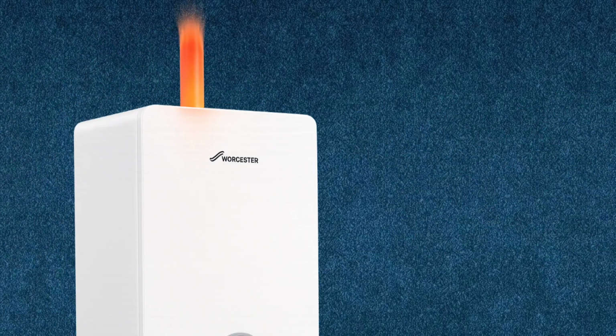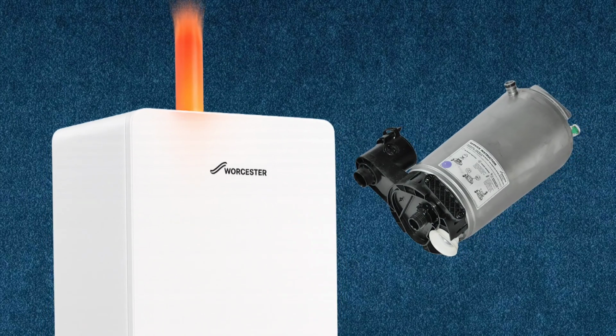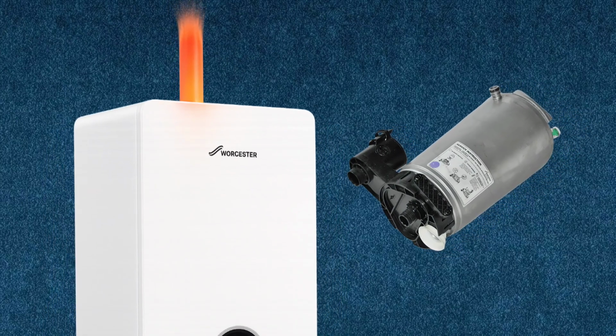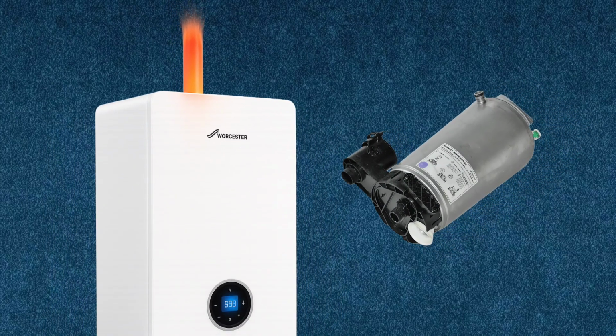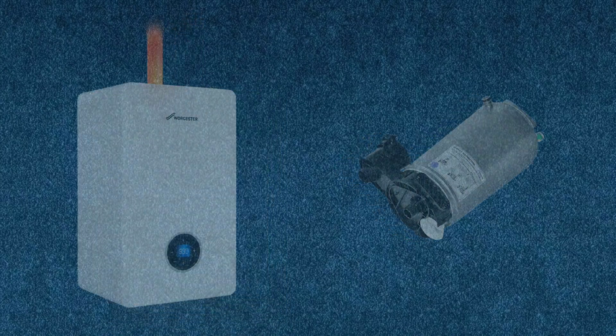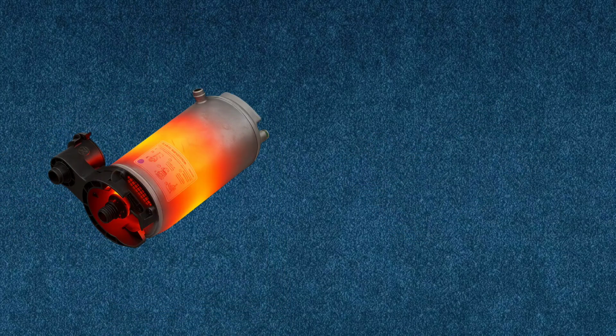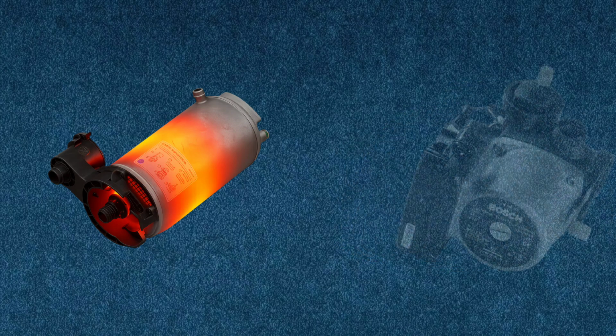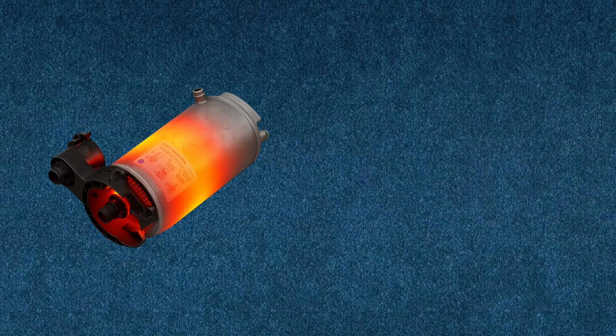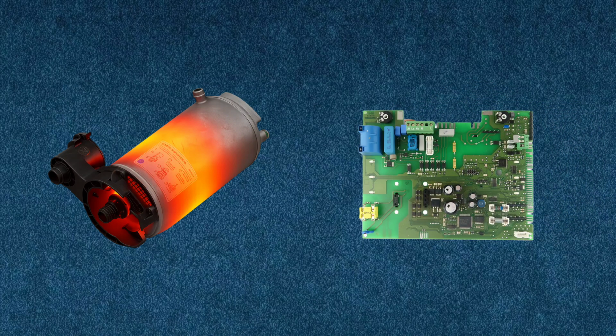Flue overheat happens when the heat exchanger gets too hot. This can be caused by a blocked heat exchanger or baffles that have been removed and not refitted correctly. Heat exchanger overheat can be caused by low system pressure, trapped air, a faulty pump, water leaks or blockages, or failed safety thermostats. Low voltage wiring issues and faulty control boards can also trigger this.